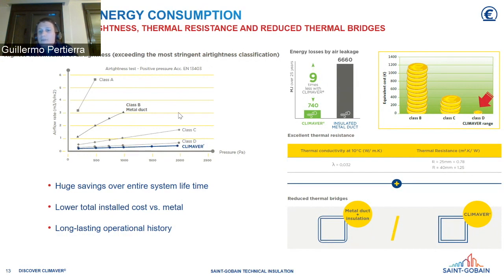And the last part is that with CLIMAVER, you can guarantee the thickness is the same around the complete surface of the duct. In some cases, when we install external insulation, we get reduced thickness at the corners, which can cause thermal bridges and condensation. With CLIMAVER, you can guarantee 25mm all around the duct.